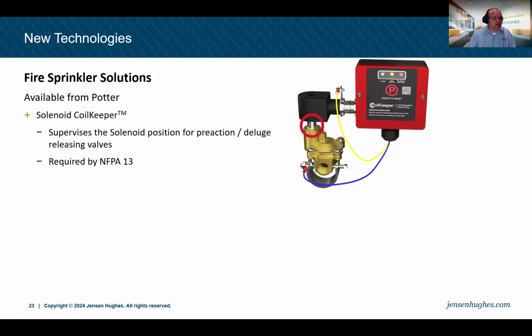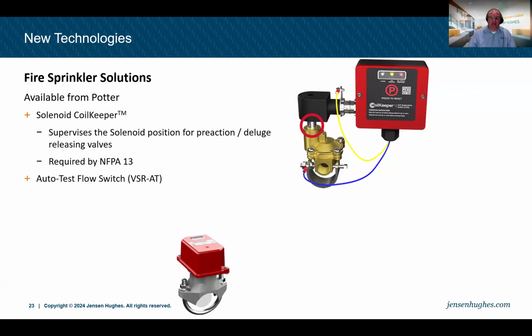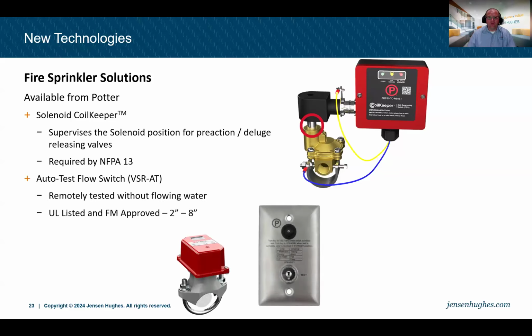This is very, very important, because a lot of pre-action and deluge systems can be easily disabled, and if they're not put back in service after an annual test, we're defeating the whole purpose of our fire sprinkler system. A second technology is an auto test flow switch. We know the proper way to test a water flow switch is with the flow of water. Well, there's a new product out that remotely tests without flowing that water. It's UL listed, FM approved for 2 to 8 inch pipe.